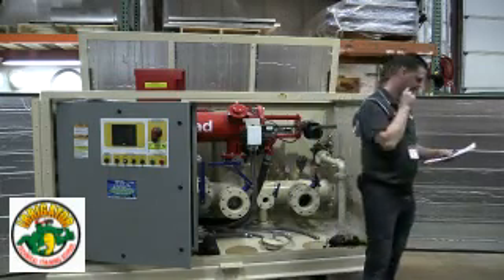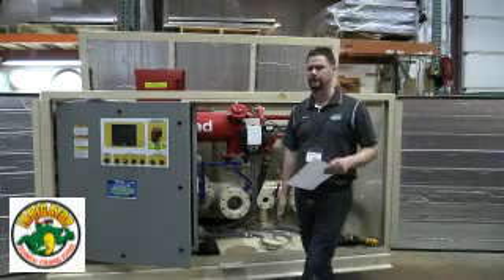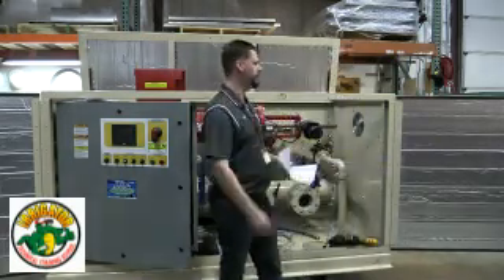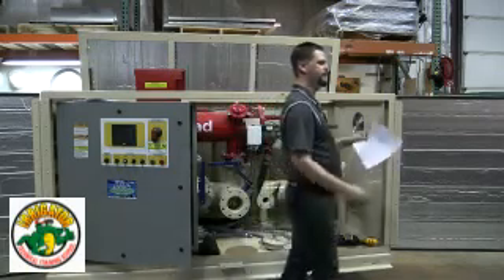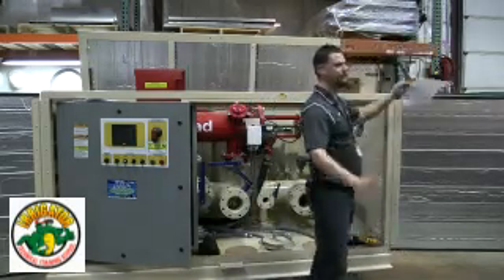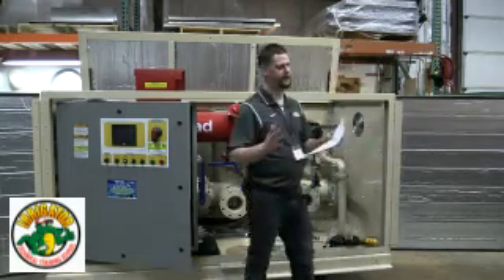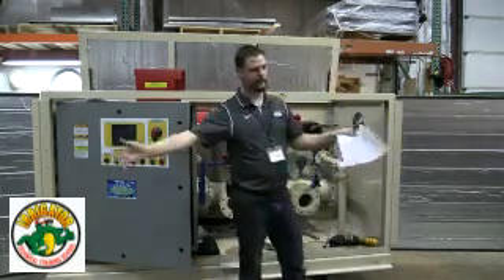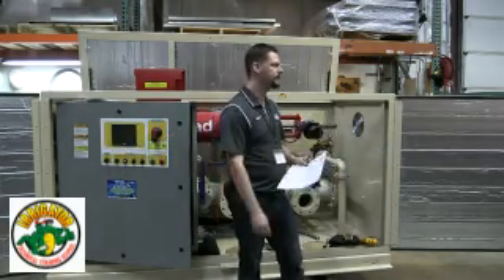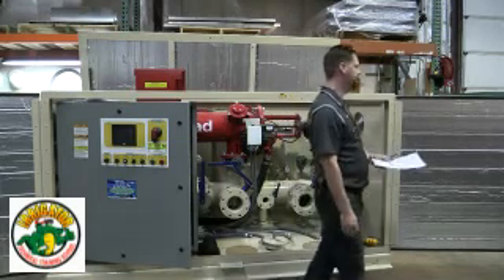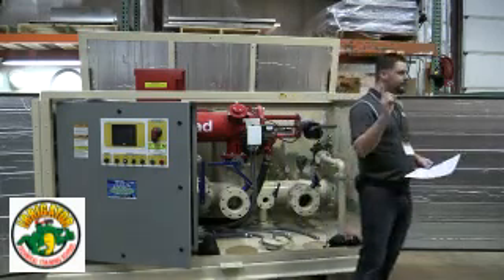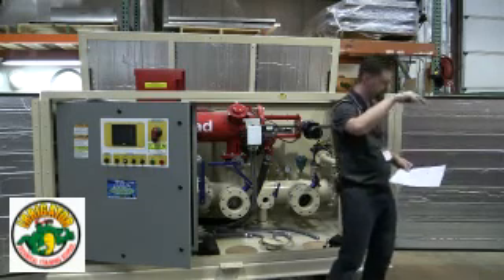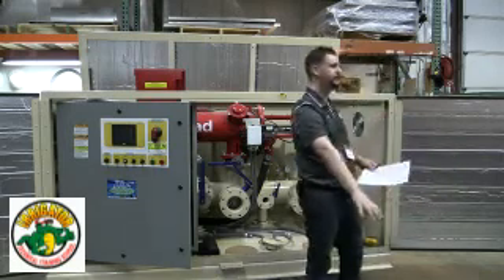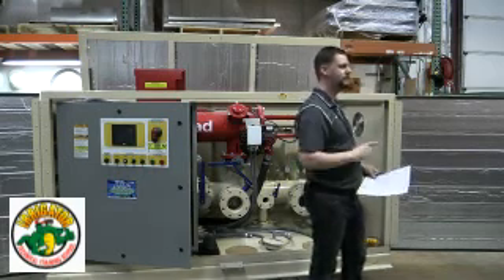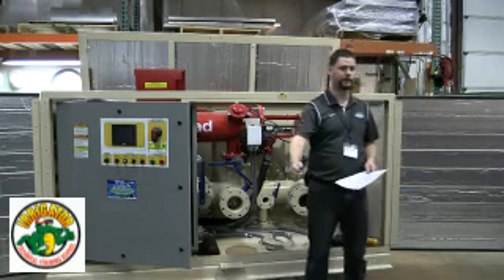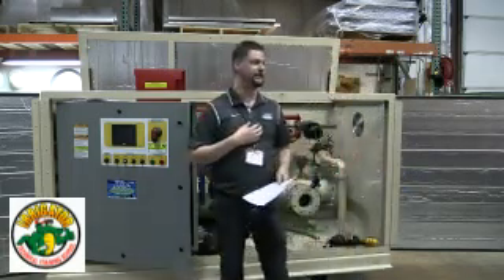All right. So, yeah, the high and low pressure switches. Now, let's go back to the low water float talk we had yesterday. The low water float length, almost always, I'm going to say almost, but we try to always make that length piece of tape when we make the pump column, which is about a foot above the intake of the pump. If you have x-ray vision, can see through the water and to the pump intake, I give you full permission to make adjustments to the length of that low water float switch.